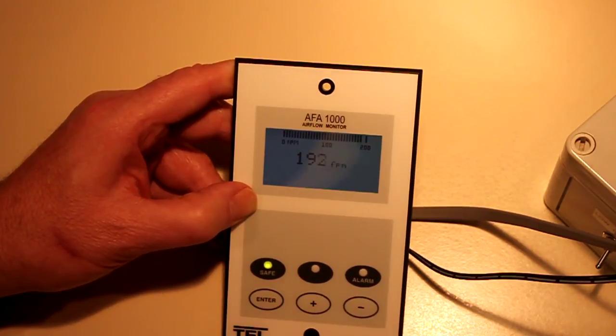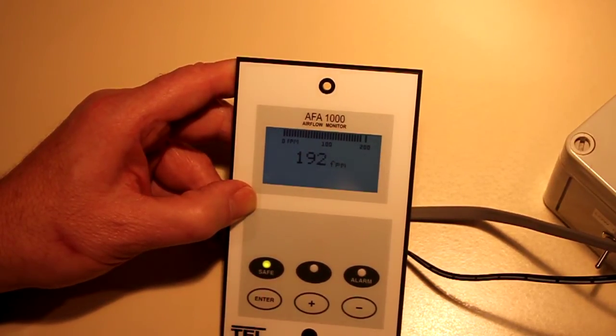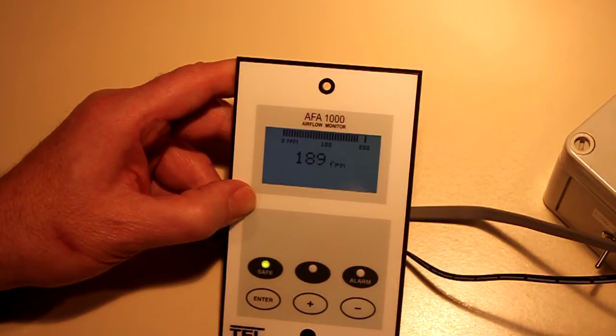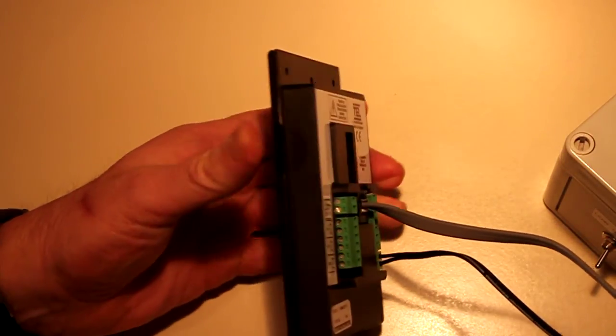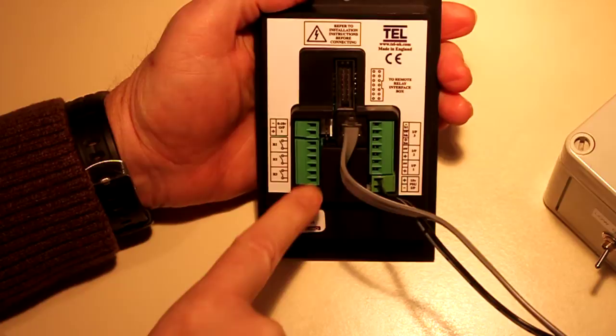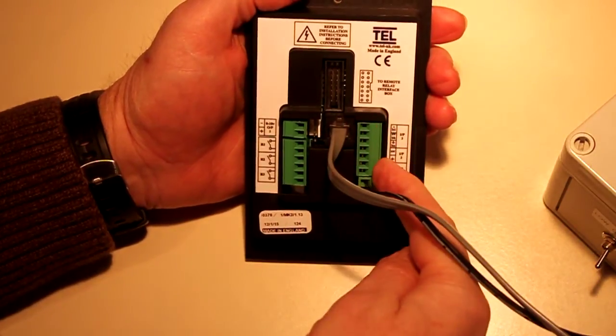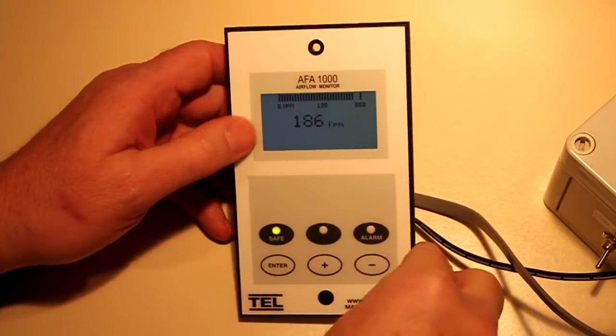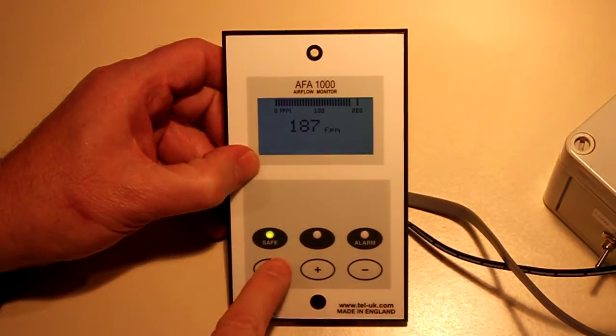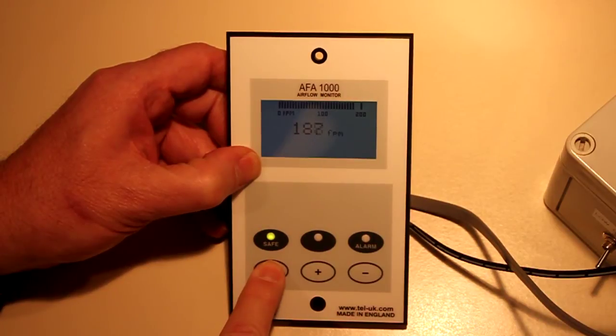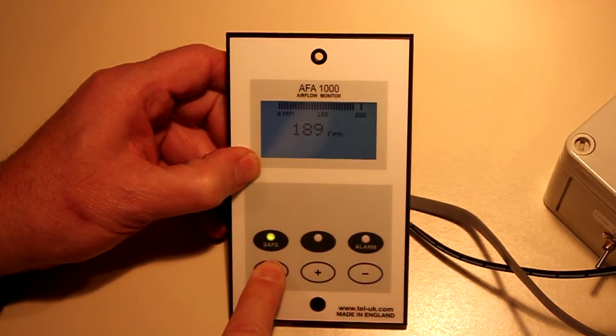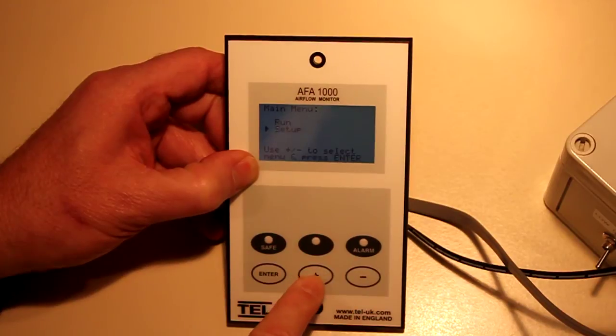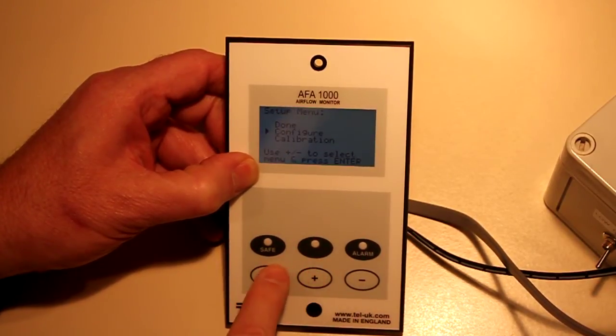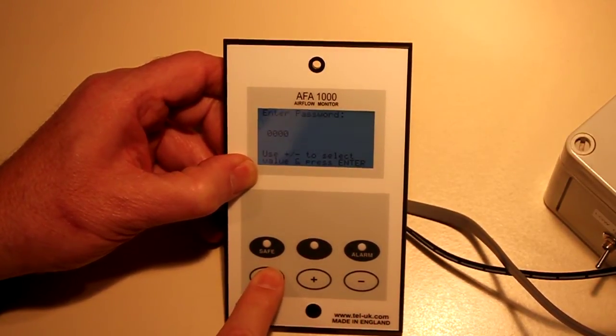The AFA 1000 has several optional functions involving connection of external equipment to the 3 volt-free dry contact relay input and output ports on the back of the monitor. Each feature is assigned to a respective relay through the Configure menu. The installer selects which input or output to configure, assigns a feature, and chooses if the relay will be normally open or normally closed. Each of the 3 inputs can be configured for alarm disable, night setback, external alarm, sash high, high-low, temperature display, or sash warning. Input 1 is factory defaulted to night setback.